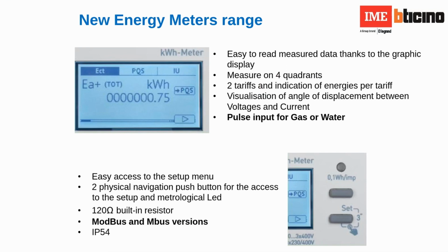Okay, so we see now a focus of the graphical display, which is capable of displaying power and energy on the 4 quadrants. So the 4 quadrants would be active, reactive energy, plus or minus, so absorbed or produced energy. We have the current and voltage phase angle. This is very important to find, for example, a bad insertion. How? If you have more than 120 degrees of distortion, this means that you have a bad insertion of the voltages. Then, regarding navigation, with a long press of the setup button entering in the setup, it is possible to view all the parameters, such as, for instance, the Modbus address, that can be changed by entering a password that you will find in our documentation.